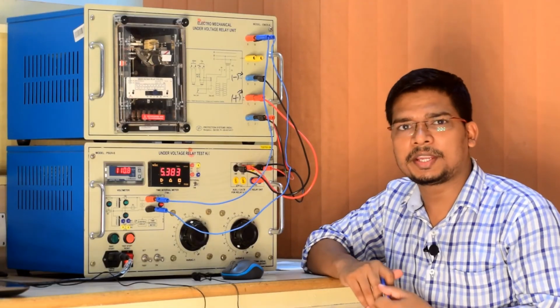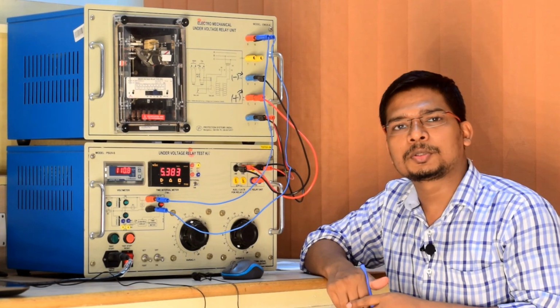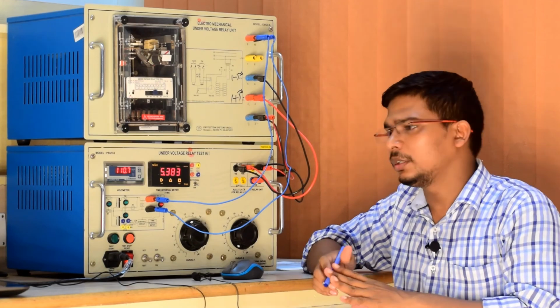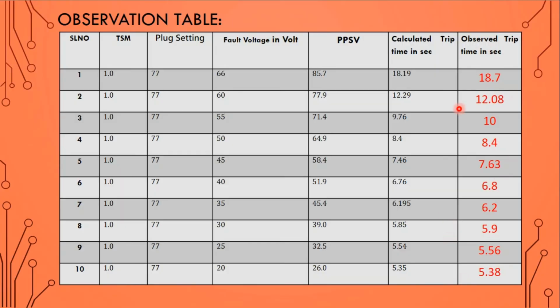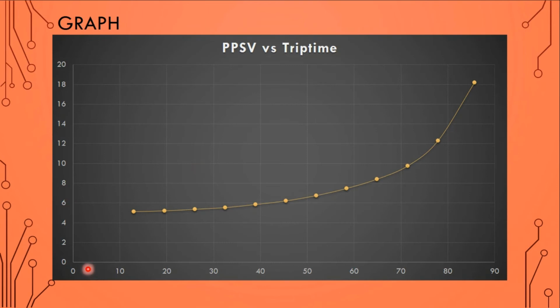So these are the observations we have taken: the expected time we calculated, and that much time we got when we operated the relay. Based on the readings, if we plot the graph, we will see how it looks. In the graph, the y-axis is the trip time and the x-axis is the PPSV, starting from 0 to 90. Whenever the PPSV is less, the trip time is less. A lower PPSV means a more severe fault, and a higher PPSV means a less severe fault, so correspondingly the time is also more. This is an inverse time characteristic. In this way you have to plot the graph.